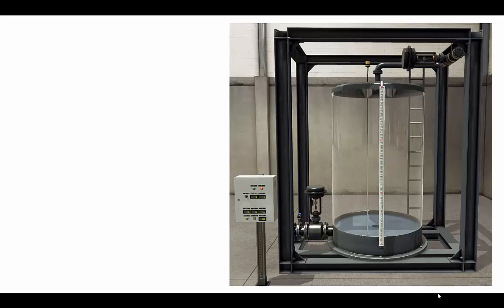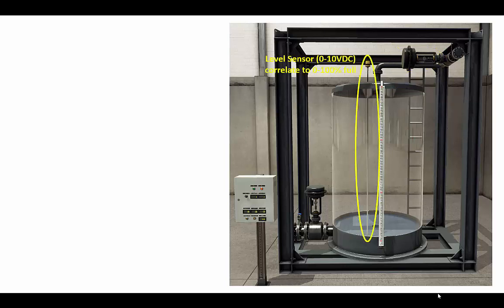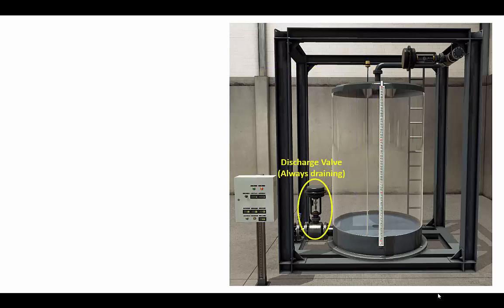I've set up in Factory I/O this tank filling station. It includes an analog fill valve that needs a 0-10 volt DC signal. It also includes a level sensor which transmits a 0-10 volt DC signal, which we'll need to scale to represent the level in the tank between 0 and 100% full. It also includes a discharge valve that I've set to always be draining — like a manual valve that someone has opened.